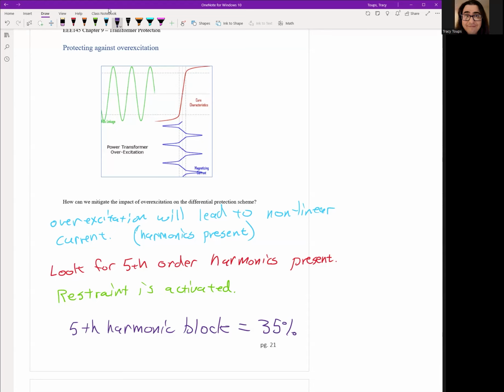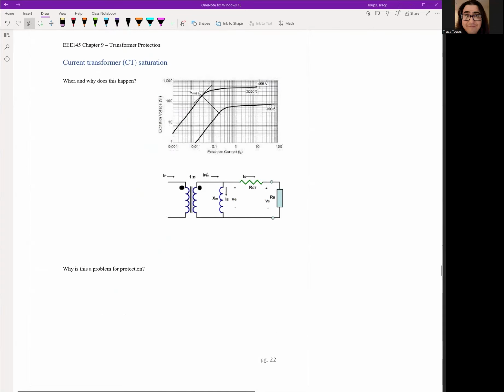One will ask, if we're looking at harmonics, how can we tell the difference between inrush and overexcitation? Well, with overexcitation, even though the waveform is messed up, it's still symmetrical across the x-axis, across the zero crossing. Just look at the blue line, it's symmetrical both left and right. Because it's symmetrical, you won't have second and fourth order harmonics. They'll be absent. You will have fifth order harmonics because the system's all messed up. That's how we can differentiate inrush versus overexcitation. Inrush is only second and fourth harmonic restraint. Overexcitation is only fifth harmonic blocking. So that pretty much solves the overexcitation issue that would accidentally cause an 87 differential to trip.